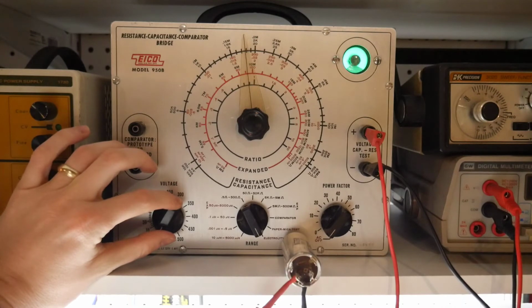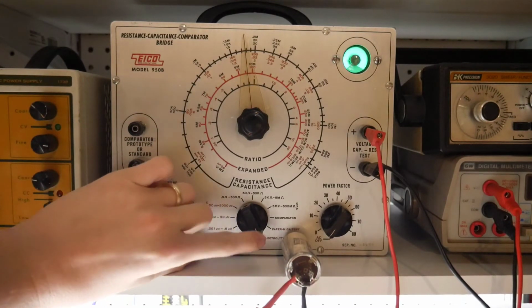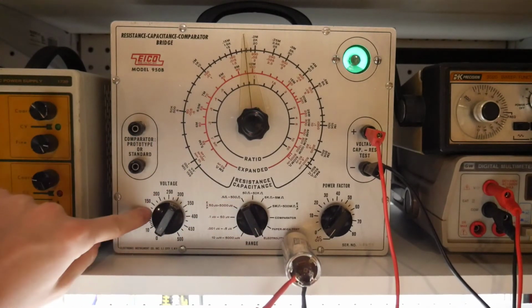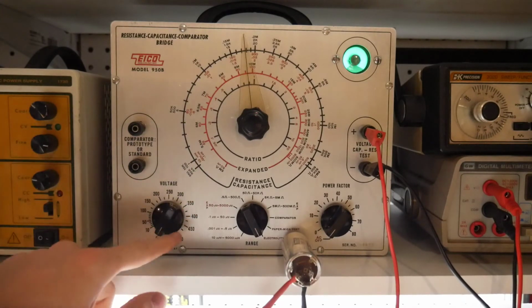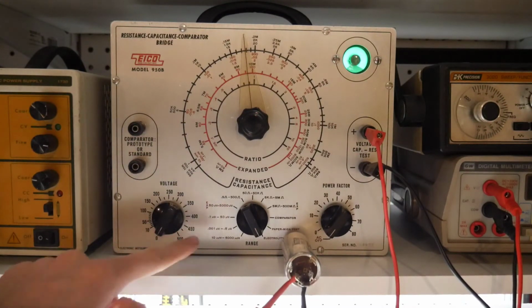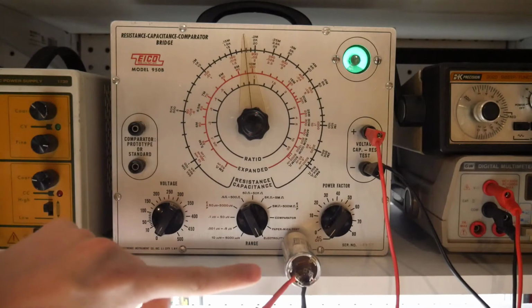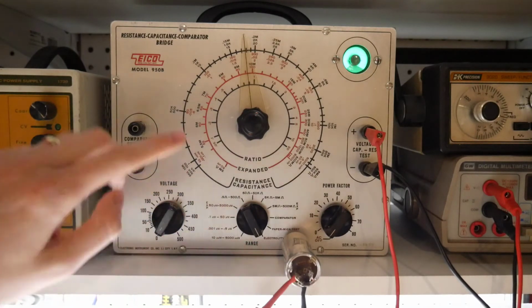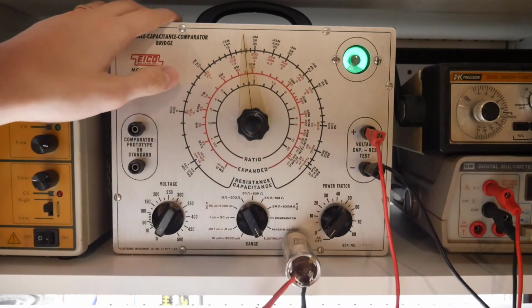One thing to note: when you have it set to electrolytic test on the range switch, and you have this voltage knob turned up, say to 400 volts, there is 400 volts on these plugs. So definitely no touching if you've got an old unit like this and you're using it.